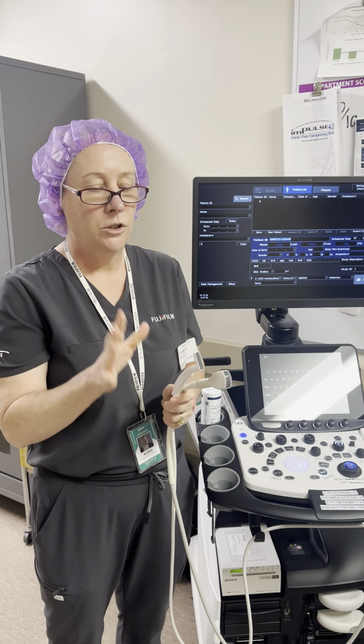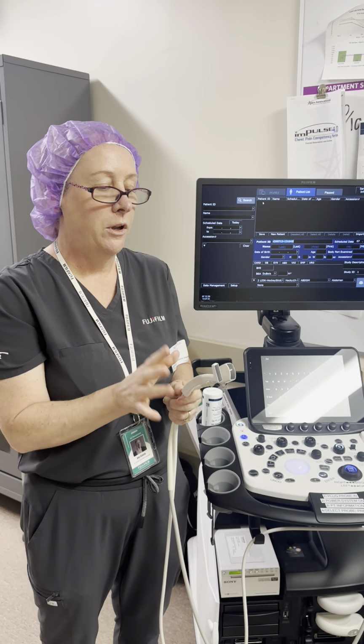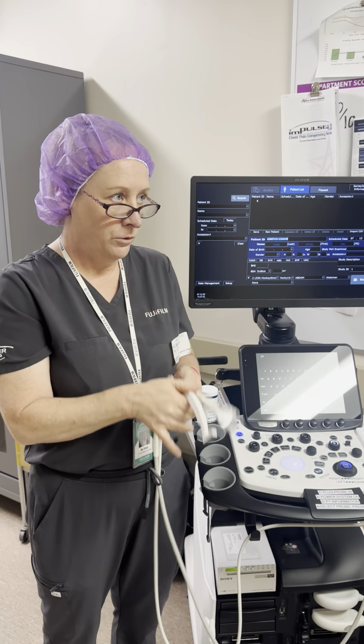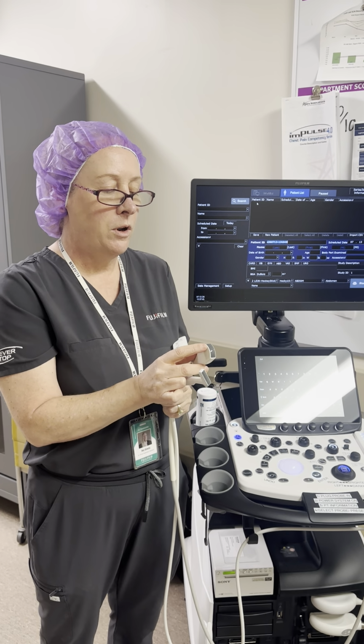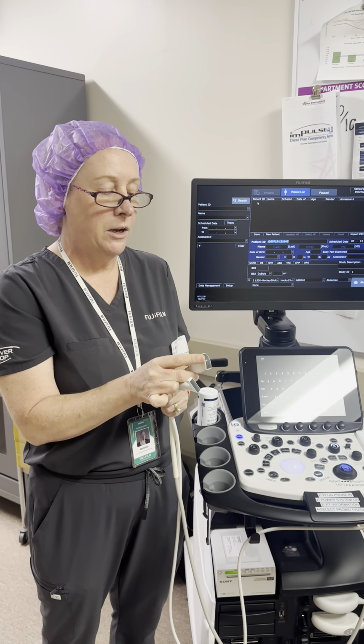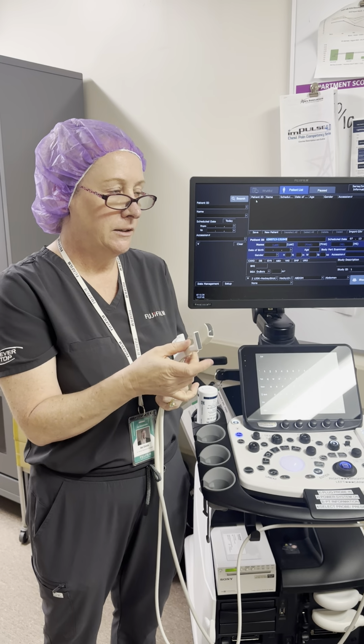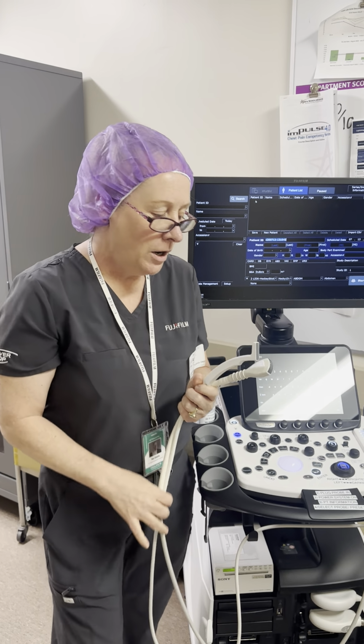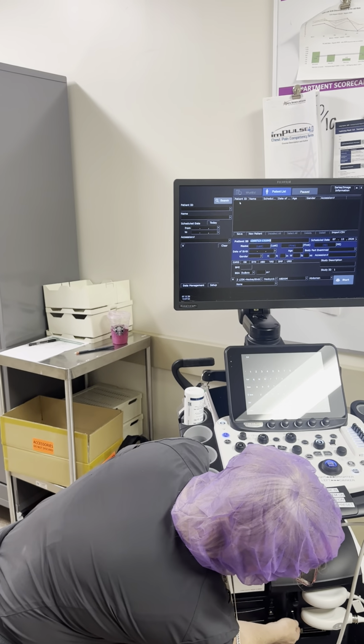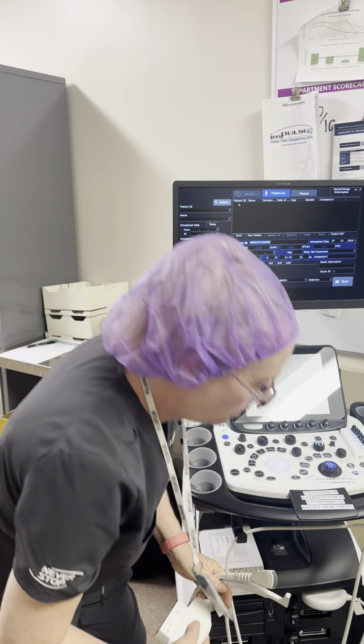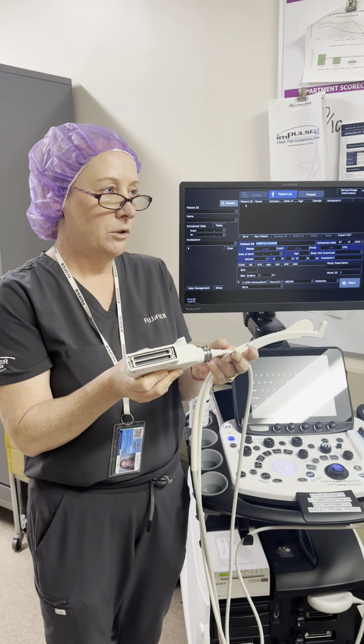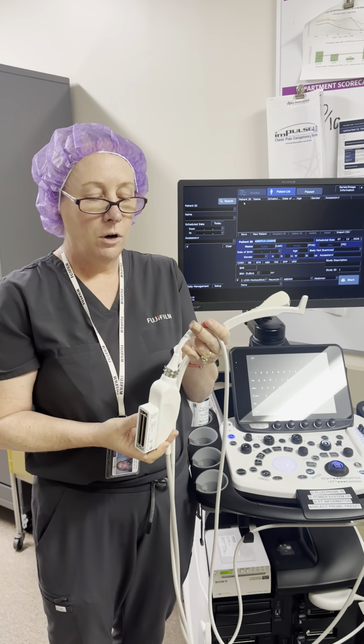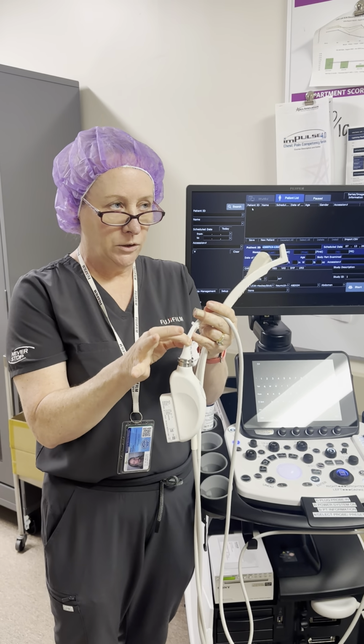For probe care, just skipping around a little bit, don't drop these on the floor. Make sure that if you're plugging them in, the matching layer is fully intact and not peeling up, and that the cords themselves, I'm just going to unlock this from here, are attached to the probe. If you are going to clean it, the immersion point is right here.